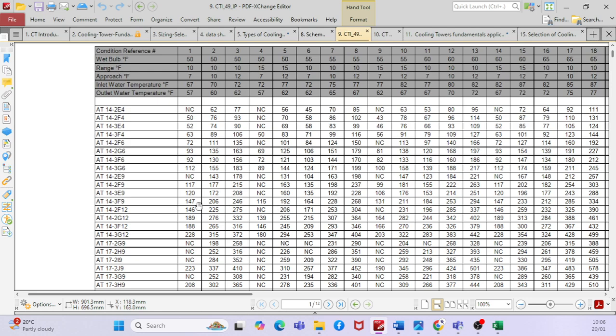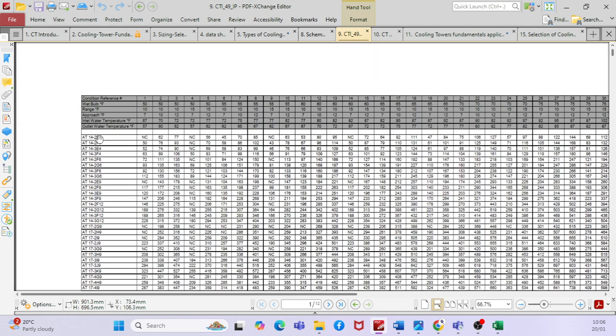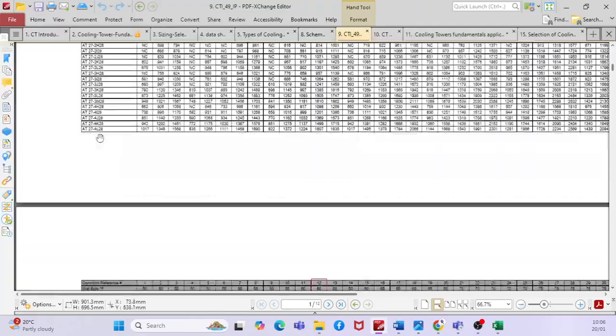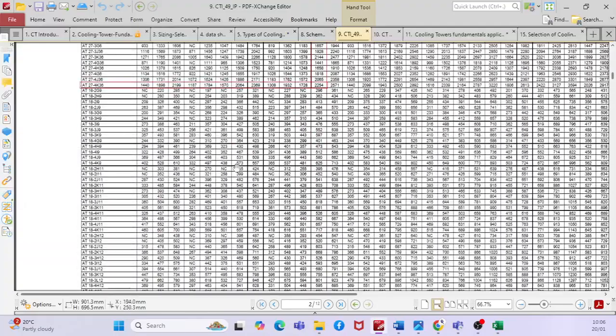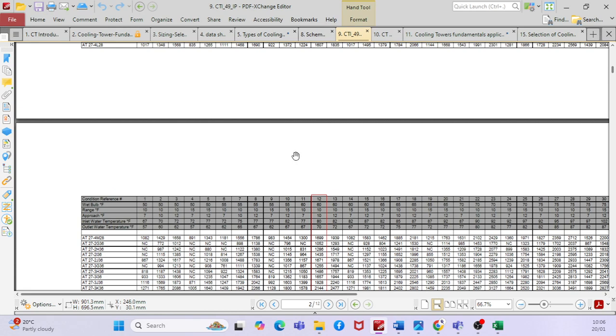Okay, you have to check the other sheet, how you have generated the corrected calculated ton, and then you have to go to the model and compare it here. Which model do you want to go to? This is the model. Clear, right? So this correction factor will be different for different conditions, right? Yes. It totally depends on how much your wet bulb is varying. You cannot always say it is going to be one particular value, like 0.6, every single time, correct? Yes, this value will change.